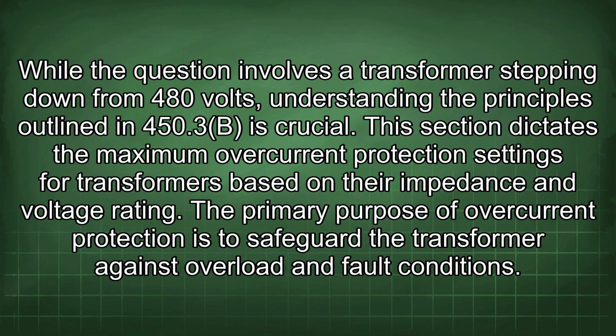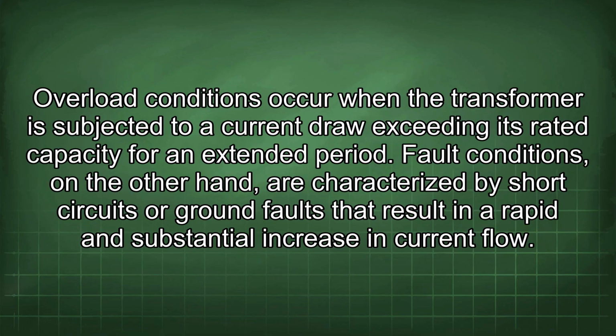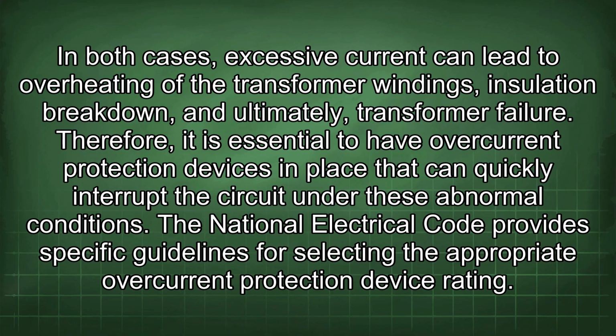The primary purpose of overcurrent protection is to safeguard the transformer against overload and fault conditions. Overload conditions occur when the transformer is subjected to a current draw exceeding its rated capacity for an extended period. Fault conditions, on the other hand, are characterized by short circuits or ground faults that result in a rapid and substantial increase in current flow. In both cases, excessive current can lead to overheating of the transformer windings, insulation breakdown, and ultimately transformer failure.